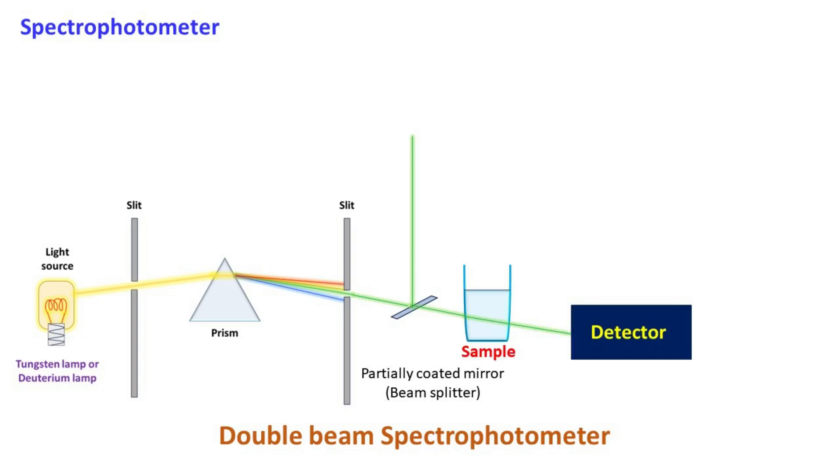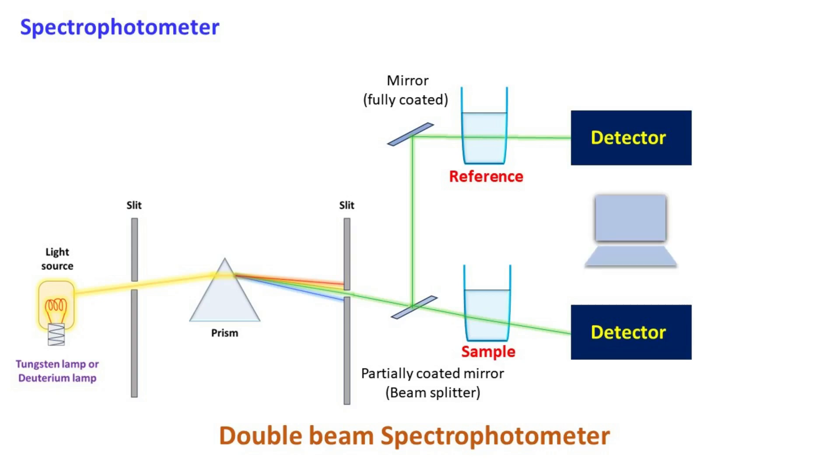One beam is allowed to enter the sample cell while the other beam is further reflected by the mirror and allowed to enter the reference cell. The reference cell generally holds the control or blank solution. The light coming out from the sample cell and the reference cell is detected by the detector and analyzed by computer.